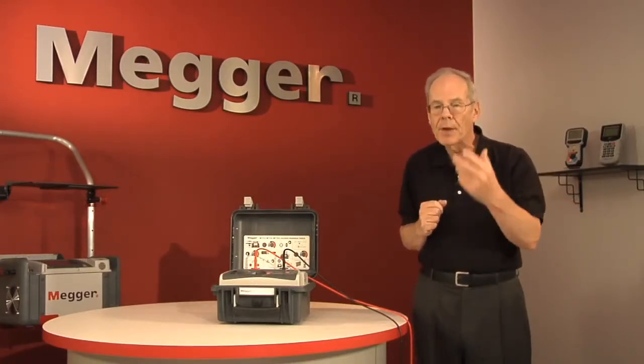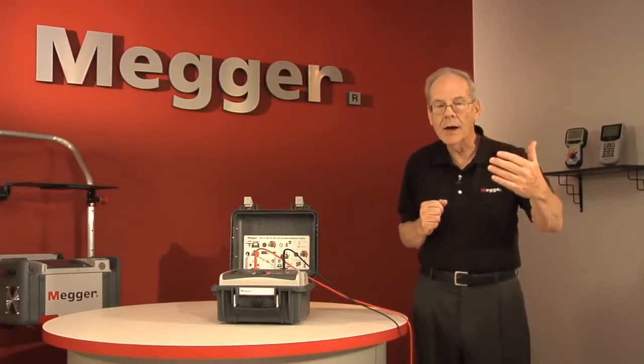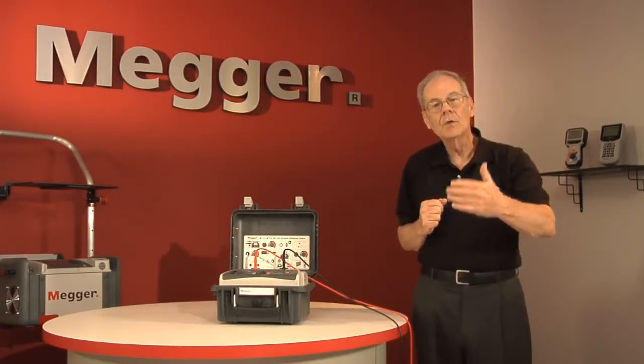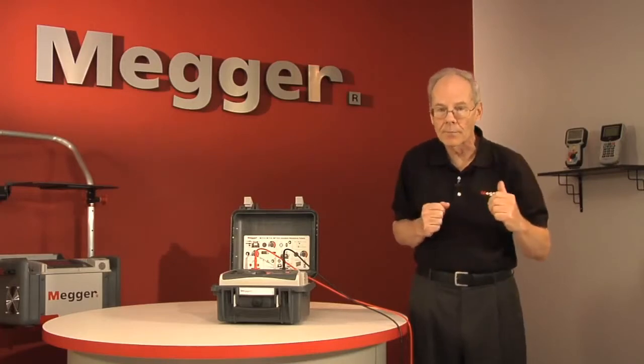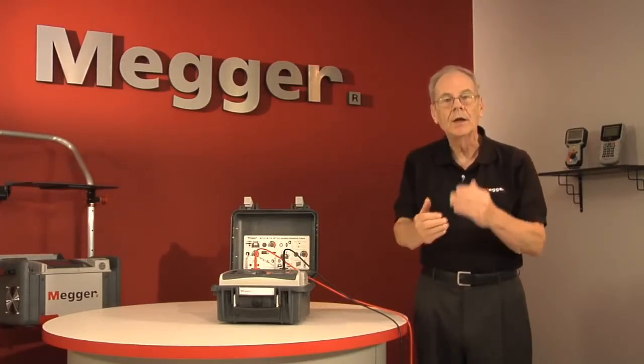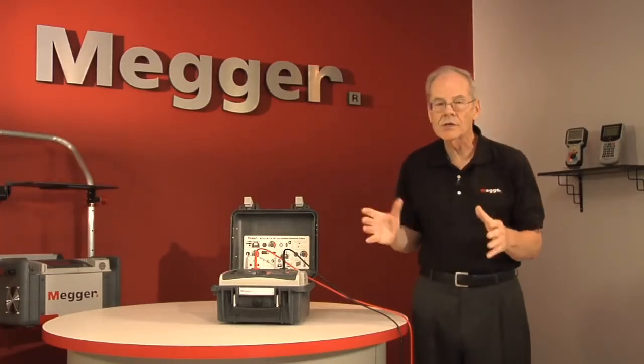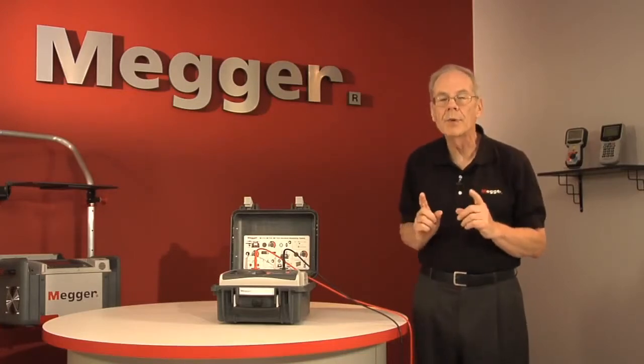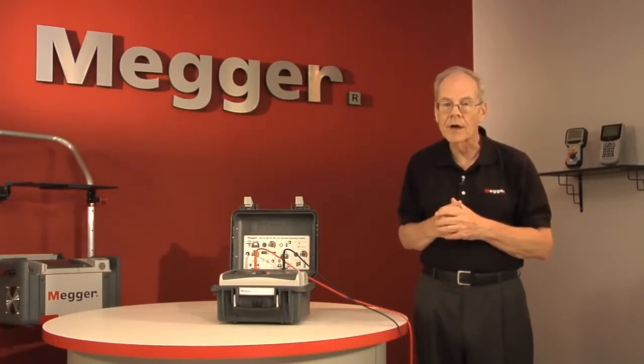So something like a pinhole, it may stand up to 2,000 volts. When it goes to 4,000 volts, it might arc, and so you'll see it. So with this test, you can isolate problems that may not have been as visible with some of the other tests.